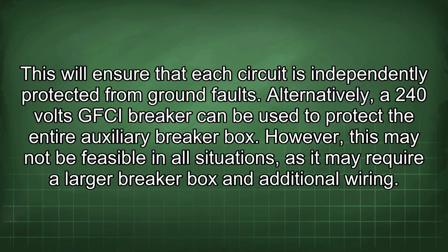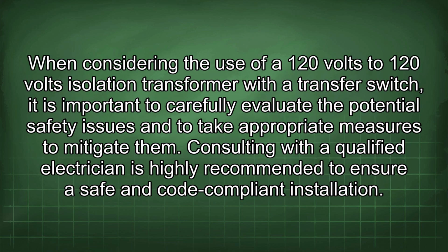Alternatively, a 240 volts GFCI breaker can be used to protect the entire auxiliary breaker box. However, this may not be feasible in all situations, as it may require a larger breaker box and additional wiring. When considering the use of a 120 volts to 120 volts isolation transformer with a transfer switch, it is important to carefully evaluate the potential safety issues and to take appropriate measures to mitigate them. Consulting with a qualified electrician is highly recommended to ensure a safe and code-compliant installation.